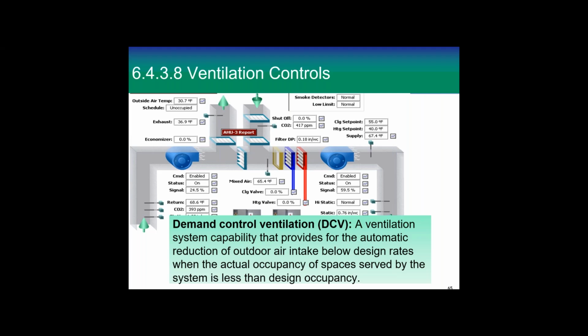And what we're trying to do is to give you a signal that says, according to ASHRAE 62, this building's safe. The demand control ventilation works off of measuring the CO2 released by a person, and that is well documented, how much CO2 a person releases at certain stress levels. And that's the same way ASHRAE 62 set their requirements. And so we say you never have to go above them. Now, I have people say, oh, if that alarm goes off that you're above the ventilation, I have to start opening the outside air damper. Well, that's not true. You don't have to. You alarm to the owner, you alarm to the operator. They make a decision on what to do. But to automatically open it would cost you energy and might not be necessary.